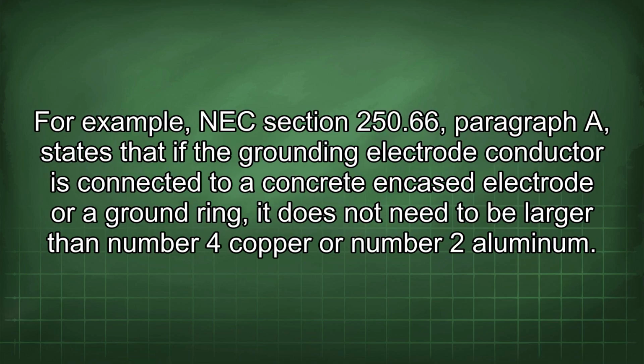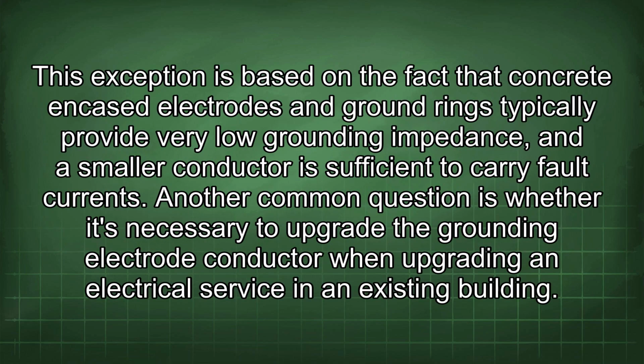For example, NEC section 250.66 paragraph A states that if the grounding electrode conductor is connected to a concrete encased electrode or a ground ring, it does not need to be larger than number 4 copper or number 2 aluminum. This exception is based on the fact that concrete encased electrodes and ground rings typically provide very low grounding impedance, and a smaller conductor is sufficient to carry fault currents.